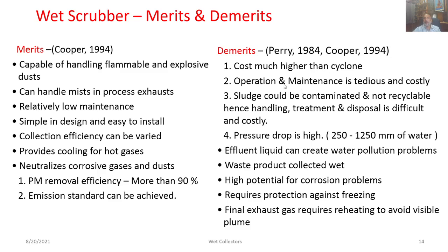Also, as far as the category of this control equipment is concerned, the cost associated is quite high, as one is expected to go through that solid liquid phase, liquid solid phase, and their separation at various stages. The operation is tedious as well as costly. Also, the sludge could be contaminated, which needs certain specific treatment. The pressure drop is quite high.